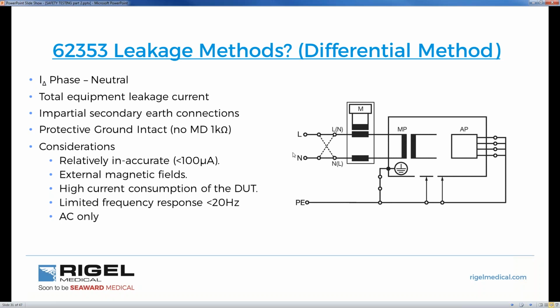So how do we measure differential leakage? We measure it by, again, I'll use the same example, 100 milliamps in the total system. If I have 100 milliamps flowing through live, and I have 99 milliamps flowing through neutral, then 1 milliamp must be missing. And that is assumed to flow through our protective earth. So I'll just reiterate that again. We have the full system is 100 milliamps. What we detect is the difference of current that flows through our live conductor and flows through our neutral conductor. And then the assumption is the missing current, through stray capacitance or dielectric resistance, flows through our protective earth. So this is why we can test on secondary earth conditions and connections within a healthcare environment.